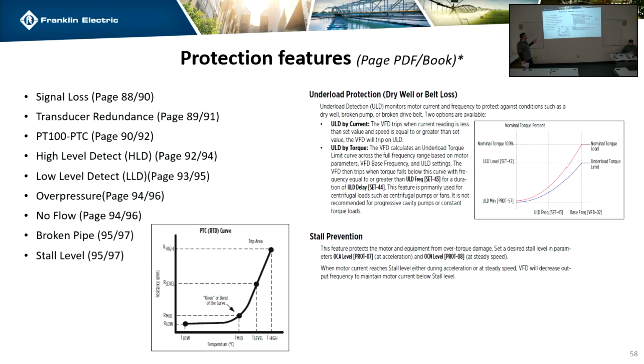So the drive can accept two transducers. That's one of the benefits of having the ACI and the AVI being duplicate. They can do everything. The only thing they can't do is just average the two. We've had that request before. The PT100 is a temperature sensor. The drive can hook right up to it. It's just built right into the drive. And with the new firmware for 1.2, the original firmware was just the setup for that. The new one has wire length calibration so that you can adjust it in the drive based on how long the run is.